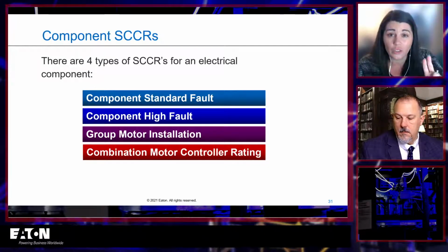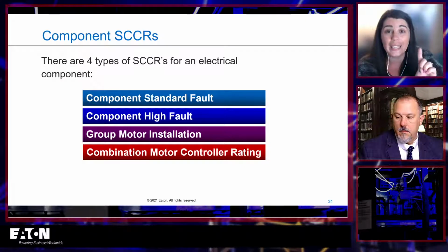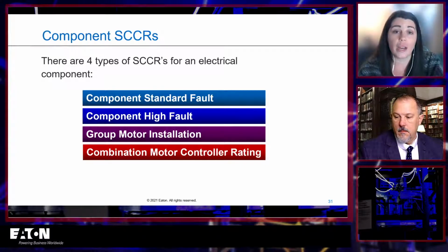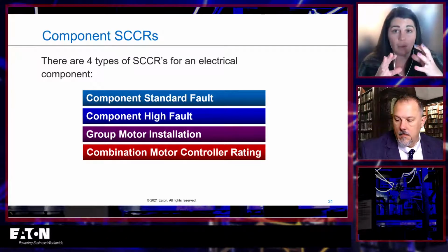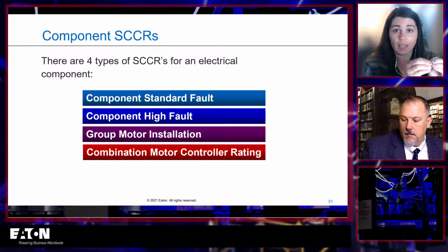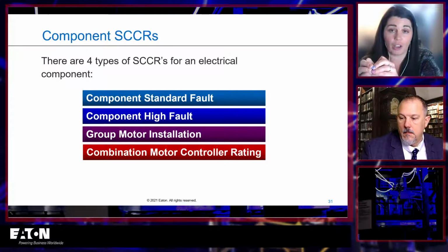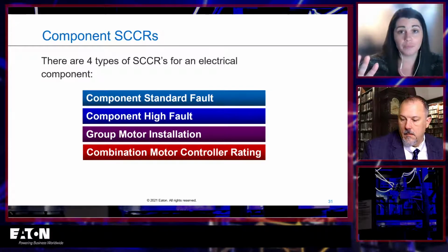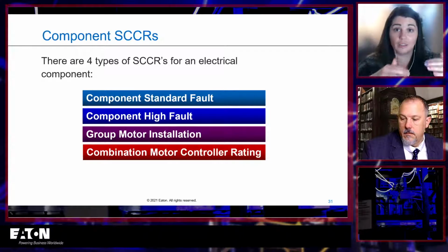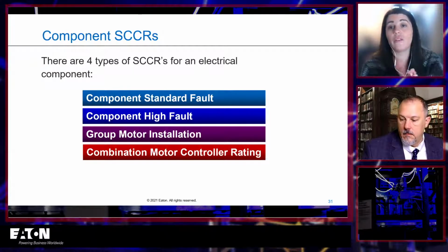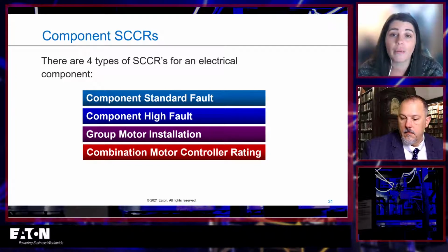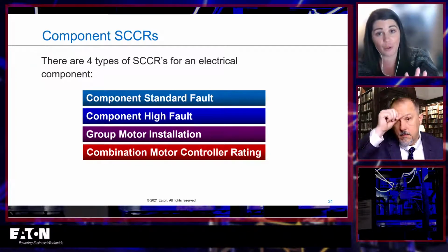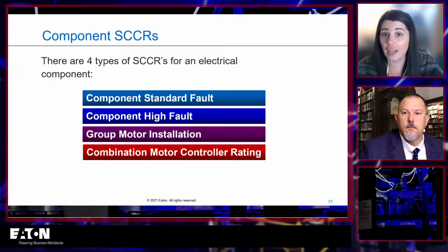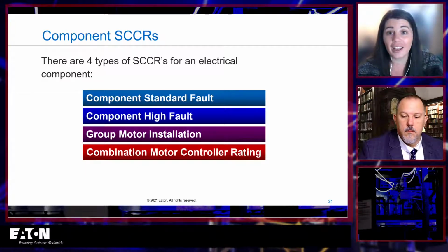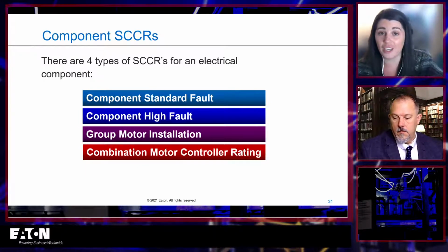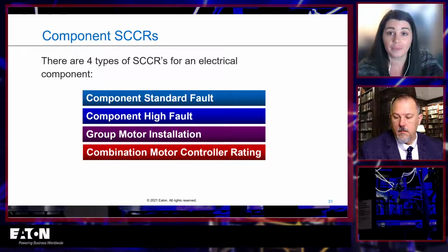It is only in the branch, and it only feeds a motor load. So a single motor load for a combination motor controller rating. What you get here is a specific combination of components. So it might be like this specific line side adapter with this specific manual motor protector with this specific contactor. All 3 of these together have a rating of X, right? So you don't have to list the 3 of them separately anymore. You say this combination of the 3 of them have this rating, and it's usually a pretty good rating. So it's not a bad rating to have. So those are the 4 main types of component short circuit current ratings that you might have for an electrical component. If you're trying to achieve a high SCCR, you're probably not going to want that standard fault rating. You're going to want one of the other ones that you can get.